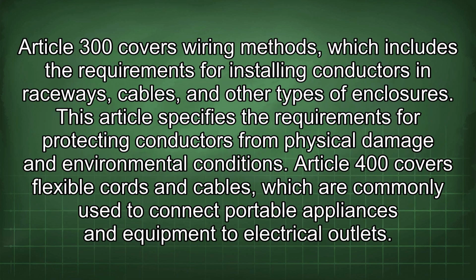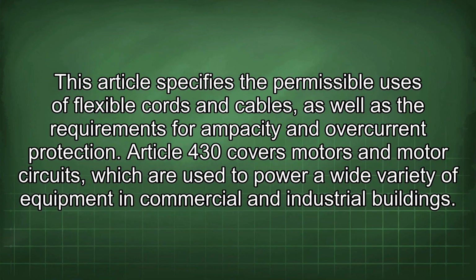Article 300 covers wiring methods, which includes the requirements for installing conductors in raceways, cables, and other types of enclosures. This article specifies the requirements for protecting conductors from physical damage and environmental conditions. Article 400 covers flexible cords and cables, which are commonly used to connect portable appliances and equipment to electrical outlets. This article specifies the permissible uses of flexible cords and cables, as well as the requirements for ampacity and overcurrent protection.